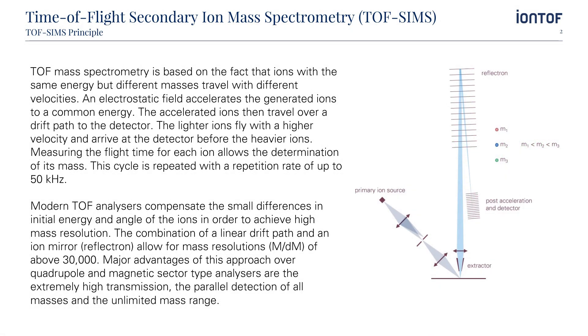TOF mass spectrometry is based on the fact that ions with the same energy but different masses travel with different velocities. An electrostatic field accelerates the generated ions to a common energy. The accelerated ions then travel over a drift path to the detector. The lighter ones fly with a higher velocity and arrive at the detector before the heavier ions. Measuring the flight time of each ion allows the determination of its mass. This cycle is repeated with a repetition rate of up to 50 kHz.